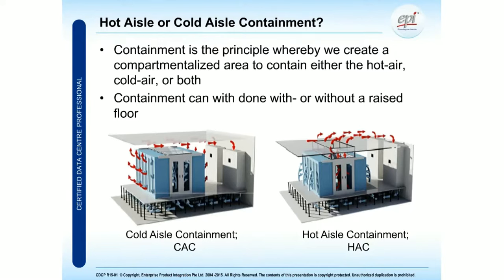Now, do we have a hot aisle or a cold aisle containment? That depends a little bit on mainly construction of the building, because originally many data centers are being designed with a raised floor system and a cold aisle contained area. So this is quite easy to implement in many cases, and by containing the cold or the hot aisle, it would mean that your efficiency level goes sky high.